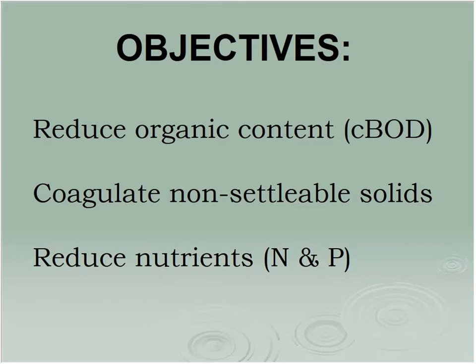Well, this is what our job is in terms of biological treatment. We need to remove what we call CBOD, that's carbon-based biochemical oxygen demand, organic matter. We have to take care of non-settleable solids. We went through our primary clarifiers. Settleable solids came out quite readily, but the non-settleable solids are colloidal material, very small particles that have no real mass to them. They don't want to go up. They don't want to go down. They just stay in the water and make it look turbid. We have to find some way of taking those out of the process. We're actually going to use the organisms to do that for us.